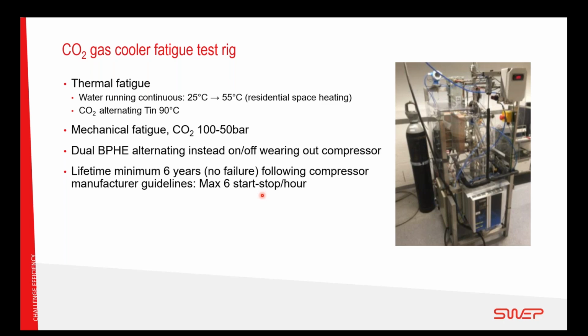And in this test rig, we built it with dual heat exchangers, so we are alternating between the heat exchangers instead of wearing the compressor out. And then we have the cooling water running continuously and the compressor feeding the heat exchanger with carbon dioxide, and that one is alternating. And under these conditions we did about 350,000 cycles without creating a failure at this point.